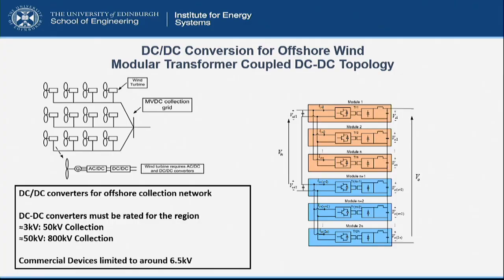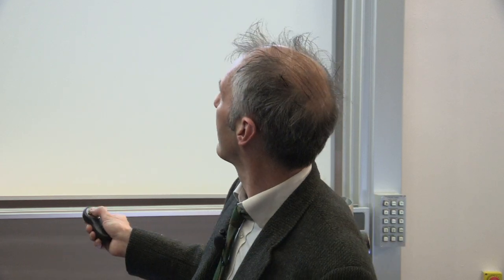The problem is, lots of concept designs showed this: we're starting off AC here, we turn it to DC, we turn it back to AC, then we turn it back to DC again at the other side. Let's get rid of some conversion stages. It doesn't work quite as easily as that, because you need to get from about 3 kV maximum from your turbine—probably less than that, a lot of them work at lower voltages—up to about 50 kilovolts, to make an efficient collection network comparable with what's done on AC at the moment. So you need to step up.